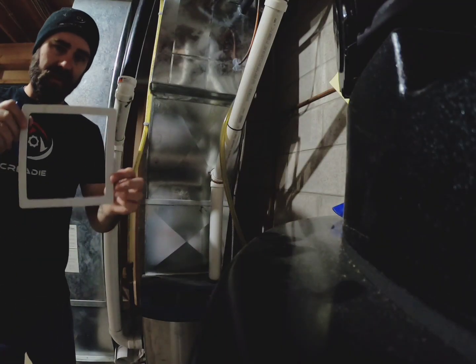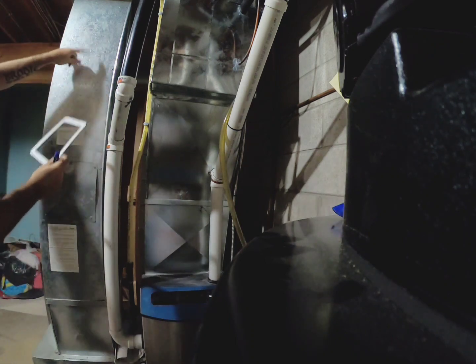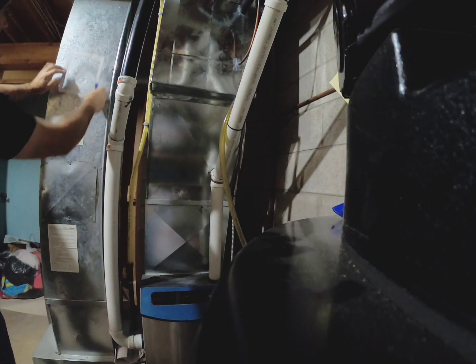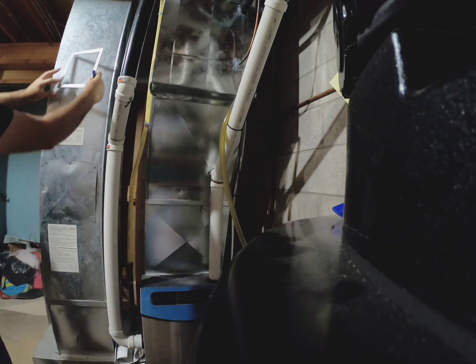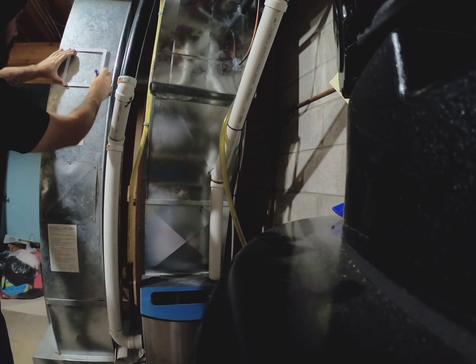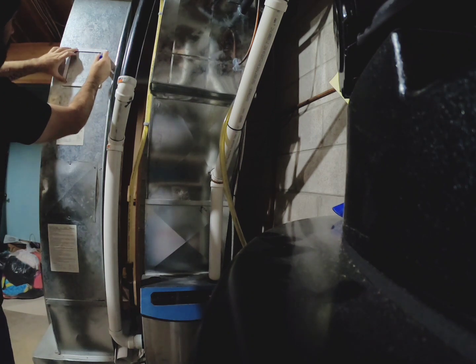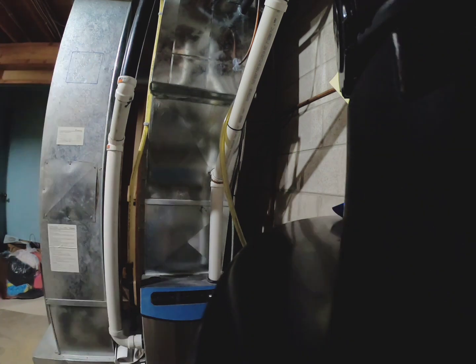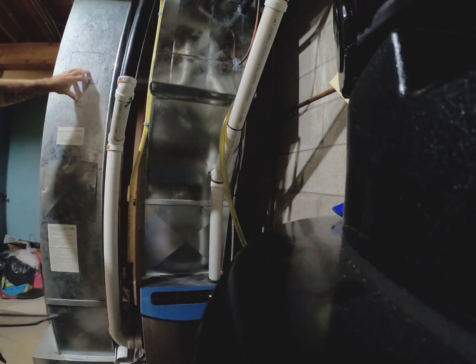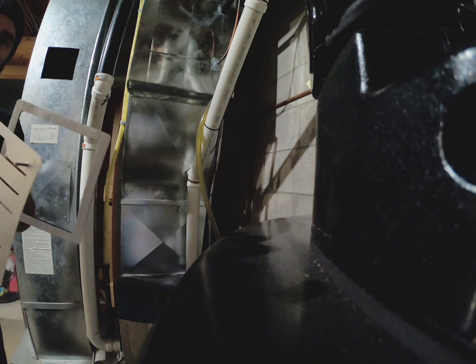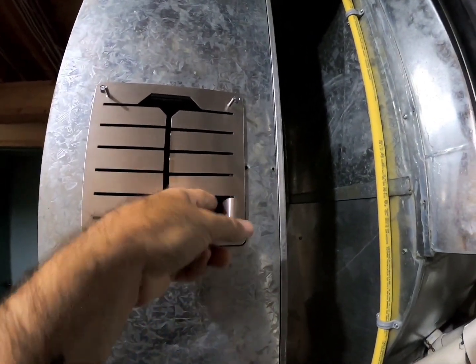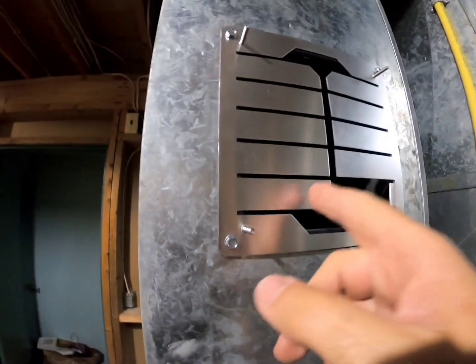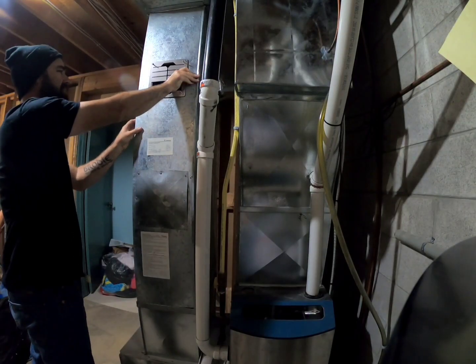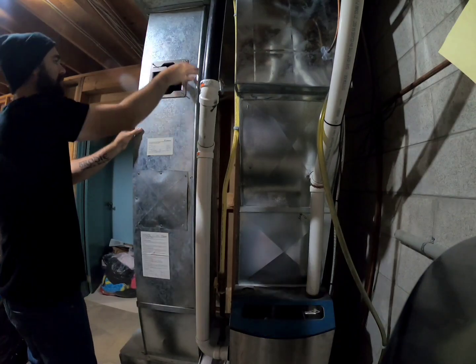So what we want to do first is take the gasket that comes with the kit, and we want to trace the inside of it on the duct here. Now, I've already taken this line and leveled it out, so I know that we're level there. So what we're going to do is trace this out. And now we need to take our tin snips and cut this portion of duct out. So we have our hole all cut out here. Now what we're going to do next is take our mounting plate and attach the gasket to the back of the plate. Once the plate and the gasket are fastened to the duct, you're going to want to screw down the plate with some self-drilling screws and bend back each individual tab.